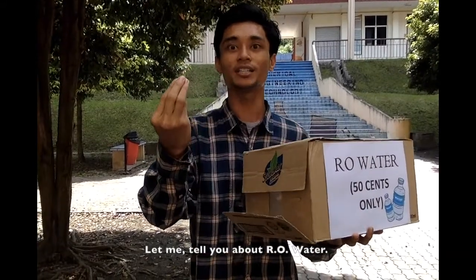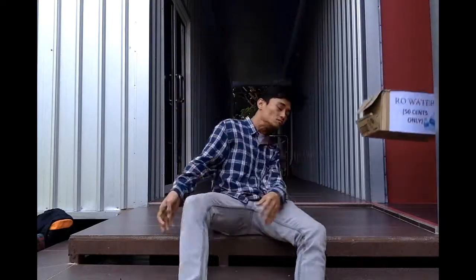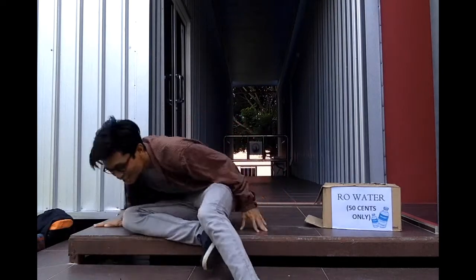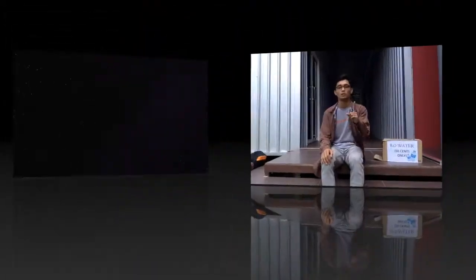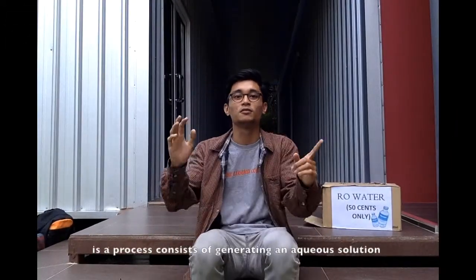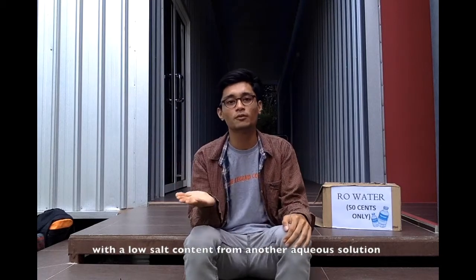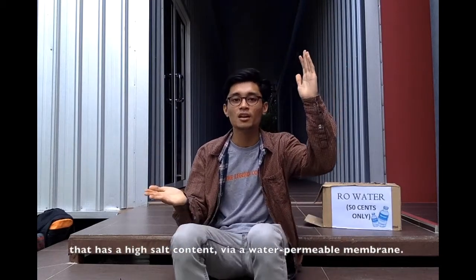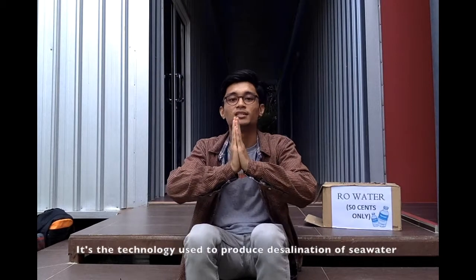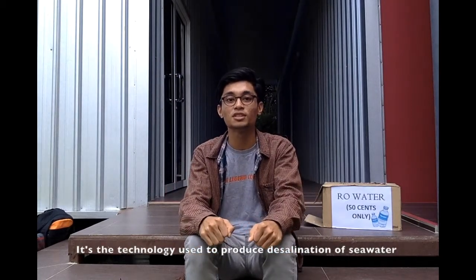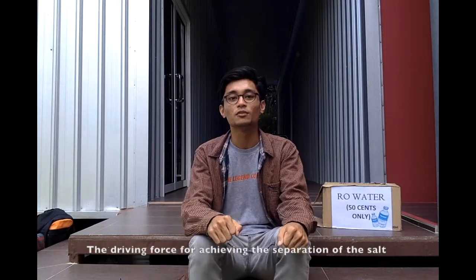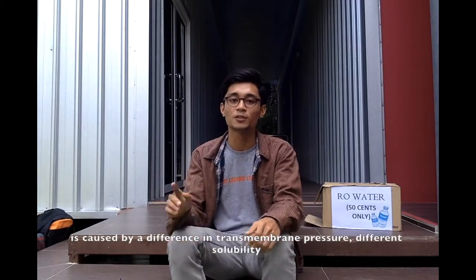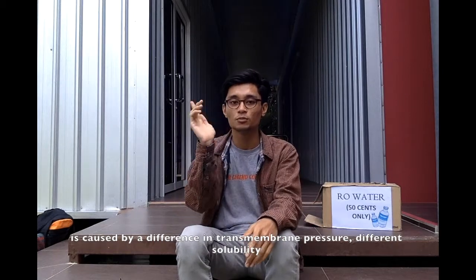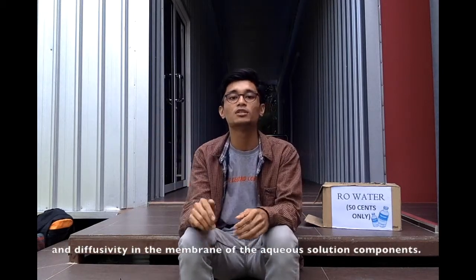Let me tell you a bit about RO water. Reverse osmosis is a process consisting of generating an aqueous solution with low salt content from another aqueous solution that has a high salt content via a water permeable membrane. It is the technology used for desalination of seawater to produce fresh water. The driving force for achieving the separation of the salt is caused by a difference in transmembrane pressure, different solubility and diffusivity in the membrane of the aqueous solution components.